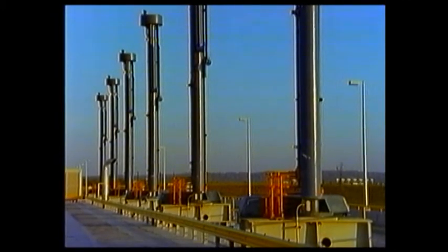At the same time, the hydraulic cylinders for the downstream gates were installed. Once installation was complete, the remaining pre-commissioning of equipment and systems was carried out prior to rotational tests. The first unit to be commissioned rotated on the 26th of April 1990 and was subjected to a comprehensive commissioning program that included synchronization and overspeed testing.